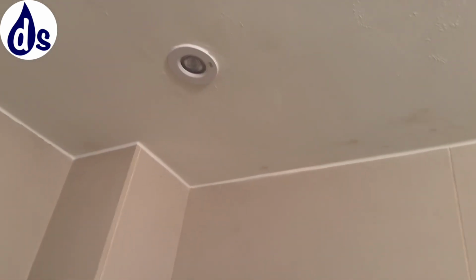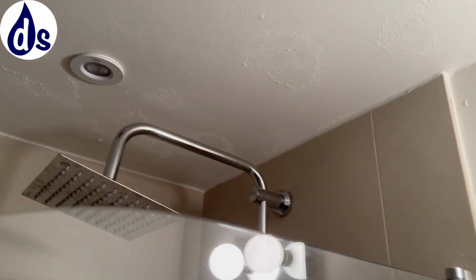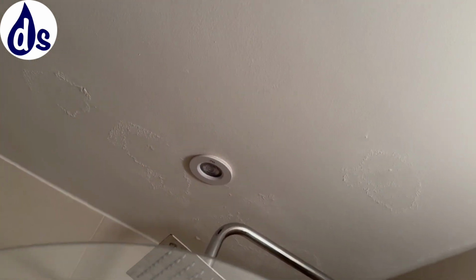And the condensation in here, in there, and there, because the fan is in the corner, so it's not the best place. The issue is that this is an internal corridor, and it means that it's not heated, whereas this is probably underneath the upstairs flat, so it's not showing as badly here as here. But a lot of bathrooms are going to have some vapor issues.